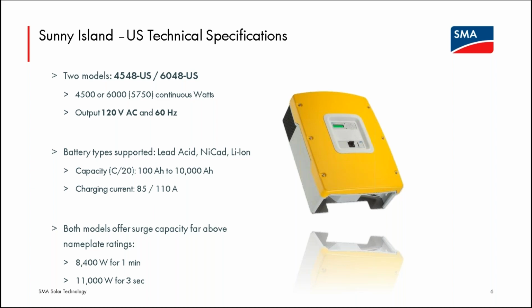The range of capacities of the battery bank vary widely. When we talk about the Sunny Boy storage, or when you hear people talk about batteries, they may talk about watt hours or kilowatt hours. For the Sunny Island, we reference the battery bank in sizes related to amp hours. Since that battery voltage is generally locked at 48 volts, you can multiply 48 by the amp hour numbers I'm presenting to get a watt hours number. So the stated supported battery size range is 100 amp hours to 10,000 amp hours. If you multiply that by 48, that's 4,800 watt hours up to 480,000 watt hours. So that's half a megawatt hour.